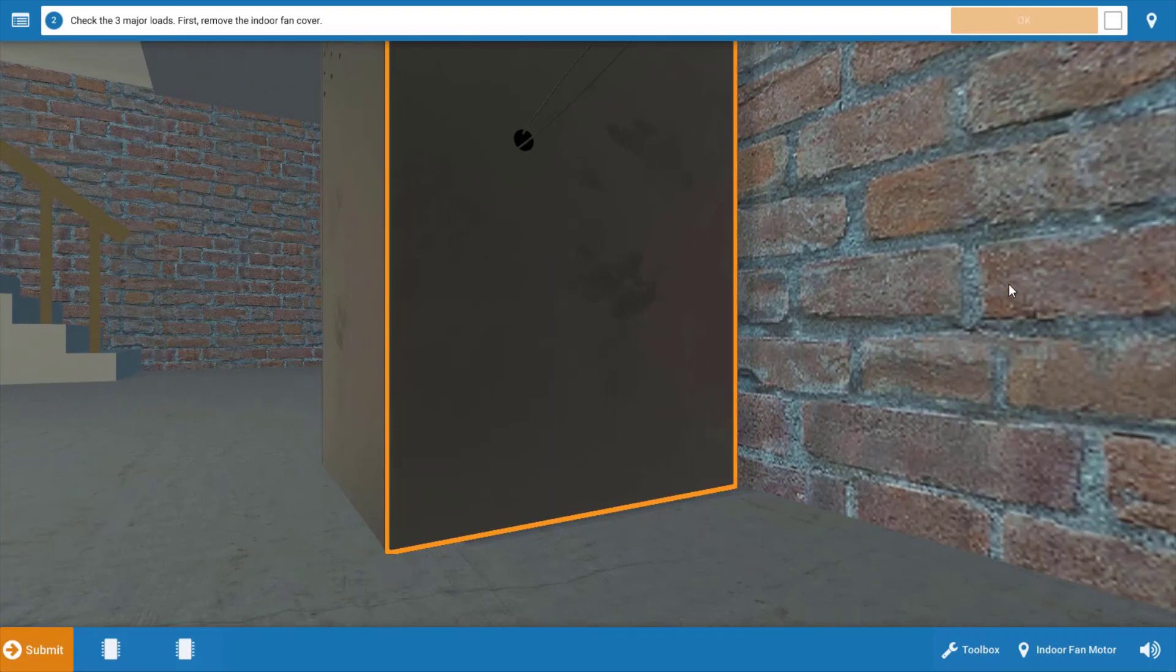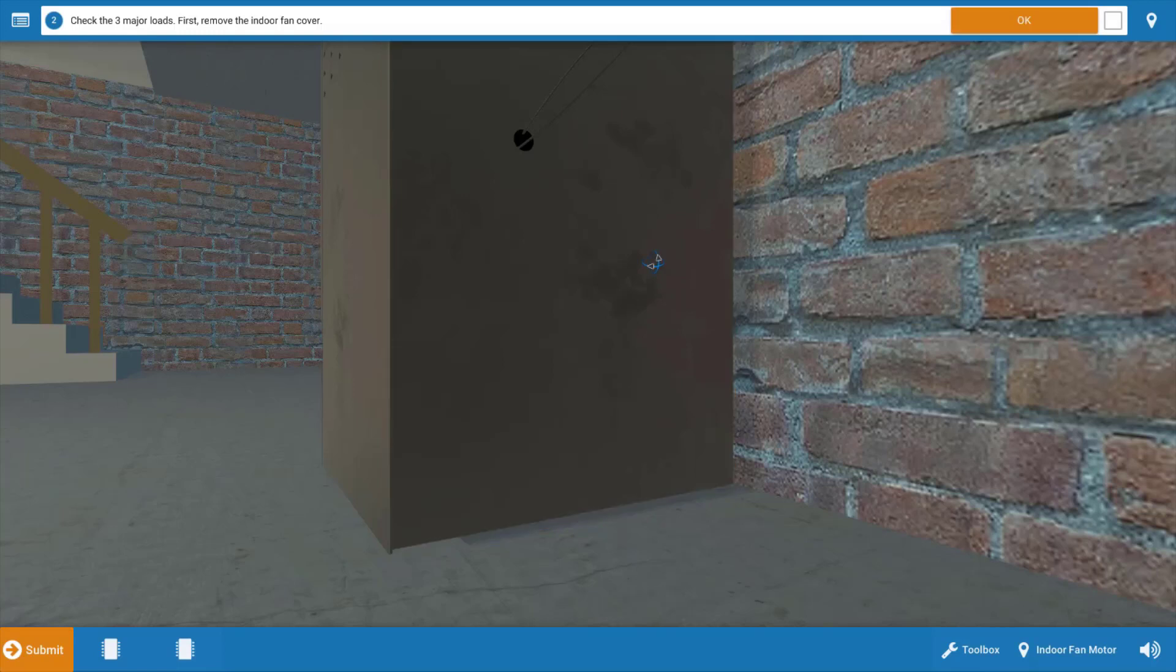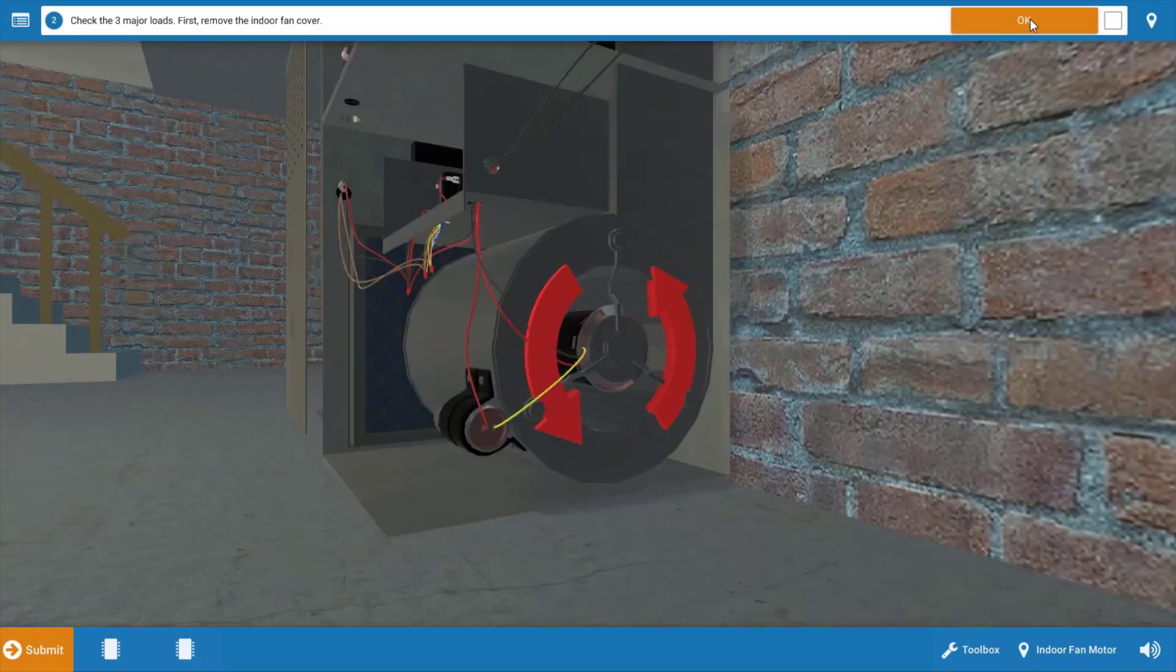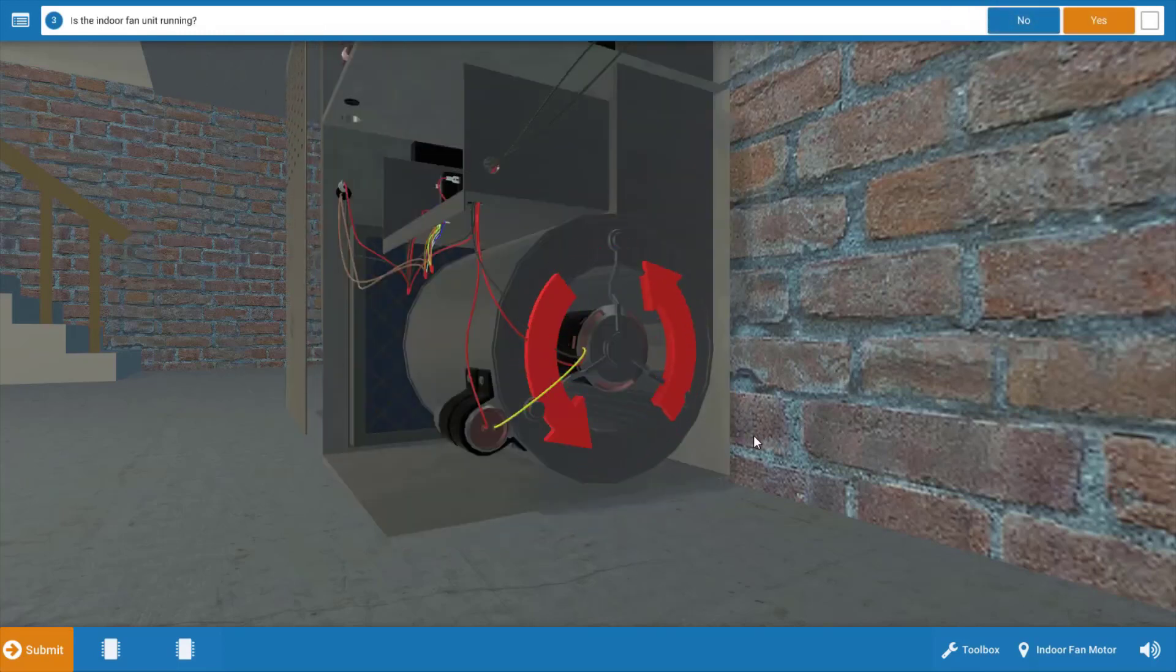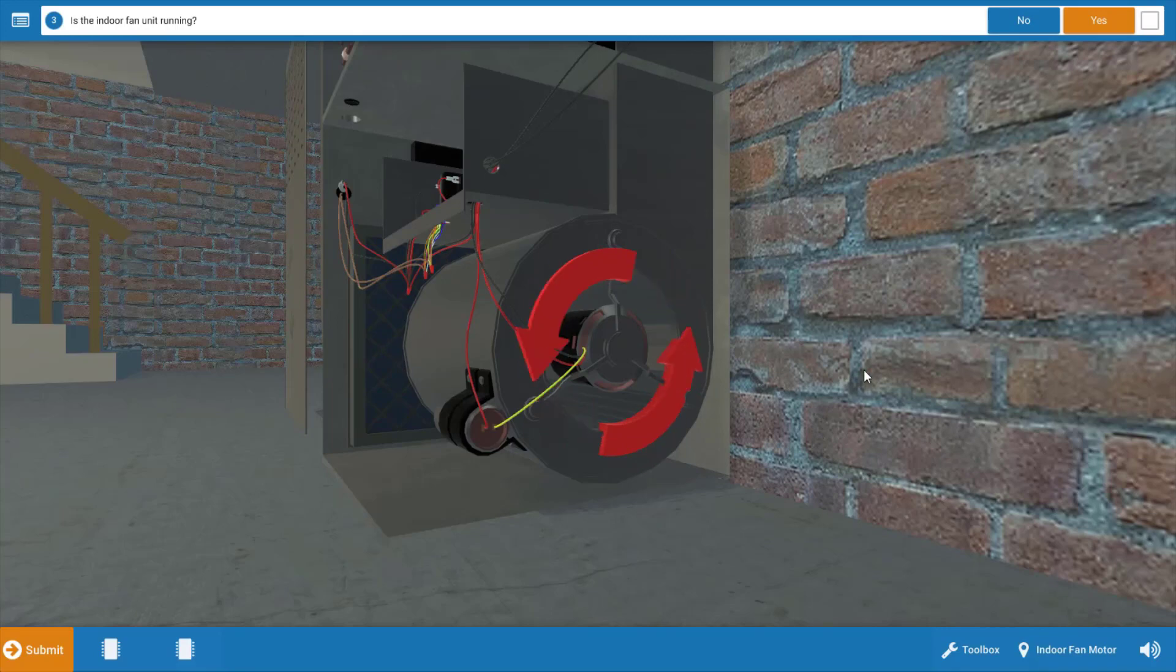Next, we want to take an inventory of which electrical loads are running. We're going to start at the indoor unit and remove the cover, click OK, and we can see that the indoor fan motor is in fact running as evidenced by the spinning red arrows here. So we're going to click yes on the procedure guide.